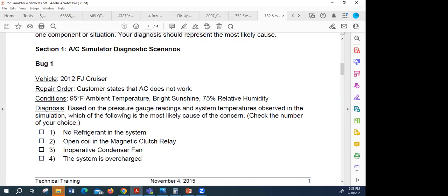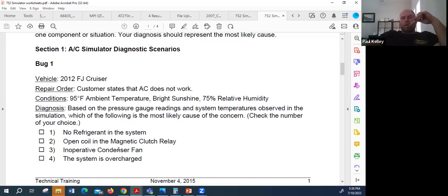So if right now all we've got, don't pick the right one, let's eliminate the wrong ones. The condenser fan, that one would cause the high pressure to be higher, not static with the low pressure. So it can't be that one. I agree with that one.